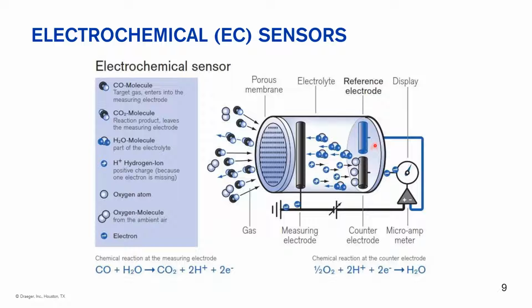We have a reference electrode in the sensor that is there so that we can maintain a constant voltage on that sensor, so that as the gas concentrations increase, the stability of the sensor stays very even, so that higher concentrations of gas don't throw off the actual response of the sensor. And then there's a third electrode called the counter electrode that basically takes the chemical reaction that's taken place on the measuring electrode and reverses it, and pretty much puts that sensor back to where it started.